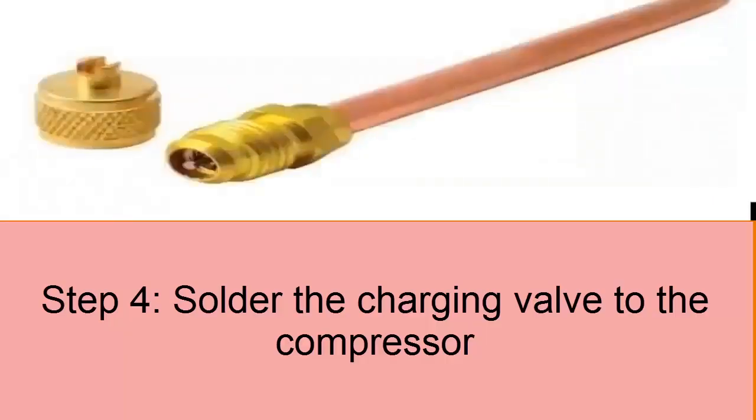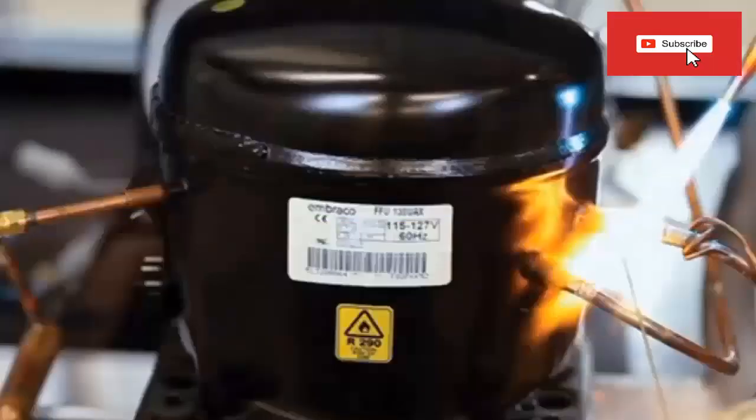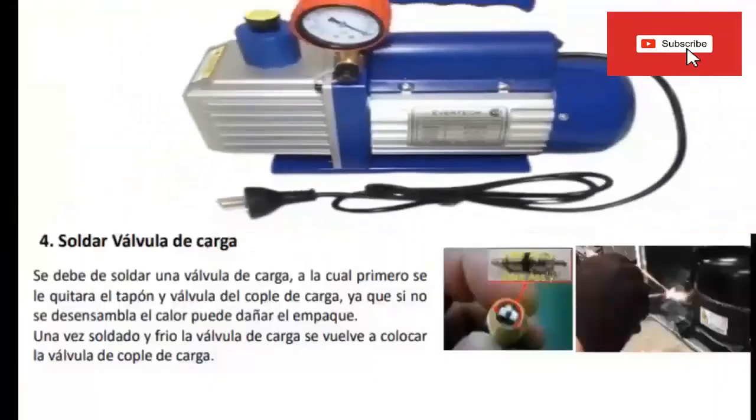Step 4: Weld Charging Valve. A charging valve must be soldered, from which the plug-in valve of the charging coupling will first be removed, since if it is not disassembled, the heat can damage the packing. Once the charging valve has been welded and cooled, the charging coupling valve is replaced.